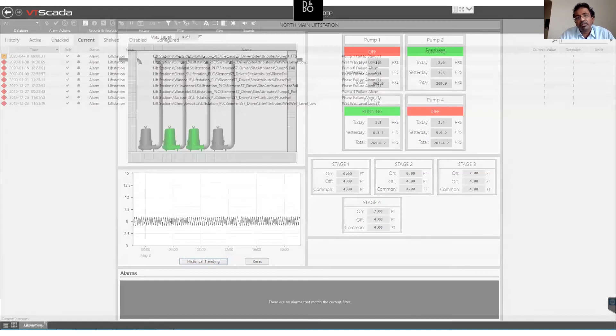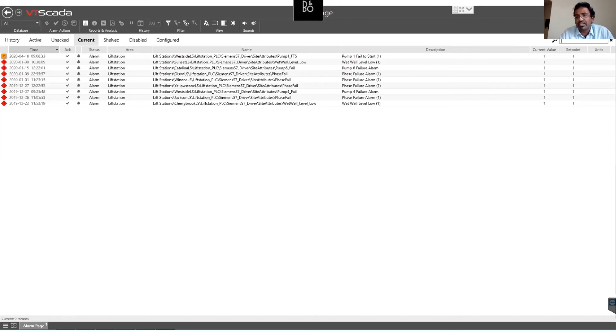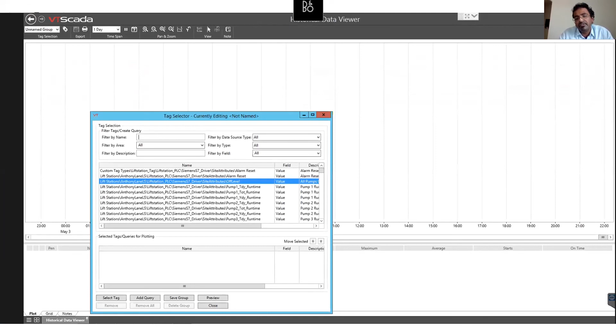Moving on, again the benefit of realm-based filtering is that the lift station operator only sees alarms active or present related to lift station sites, and doesn't have to look at any other alarms that are part of the same system since they don't belong to his realm. Similarly, realm filtering filters out historical data to only show the subset relevant to the lift station operator.